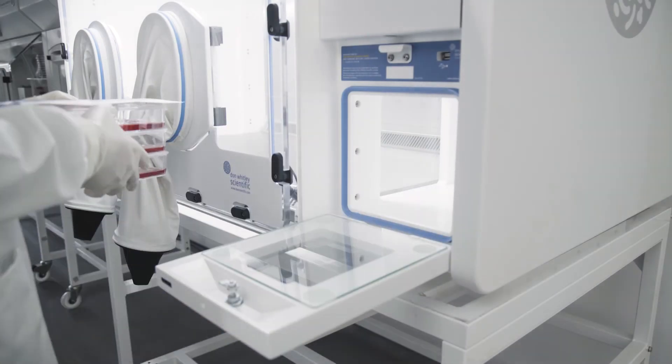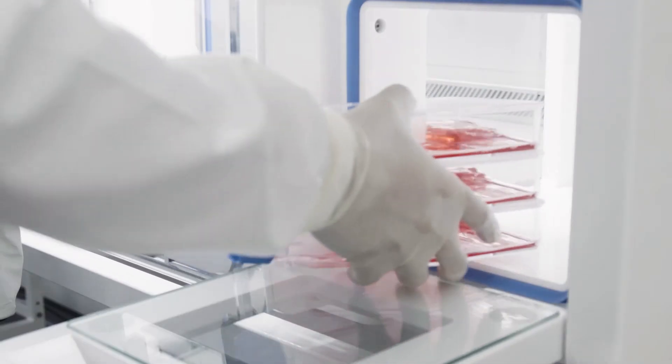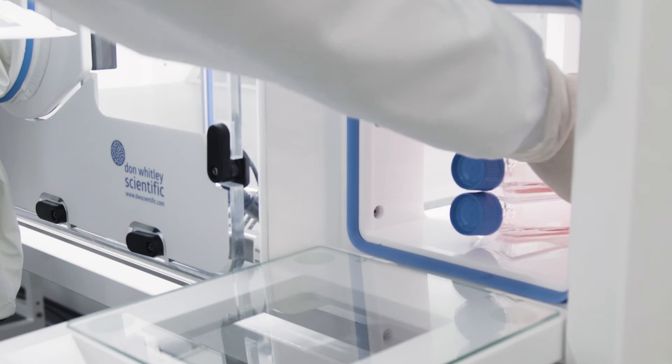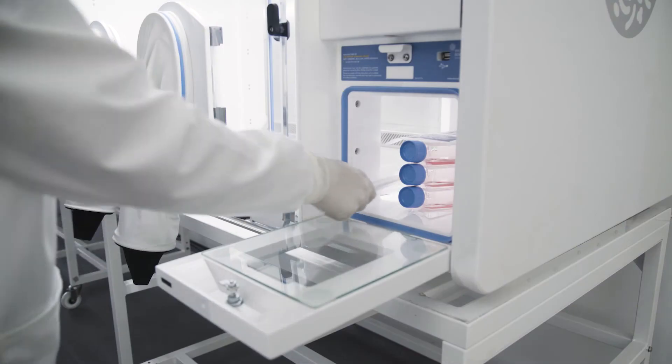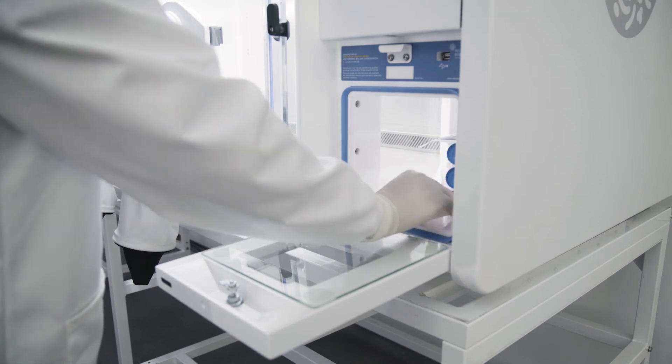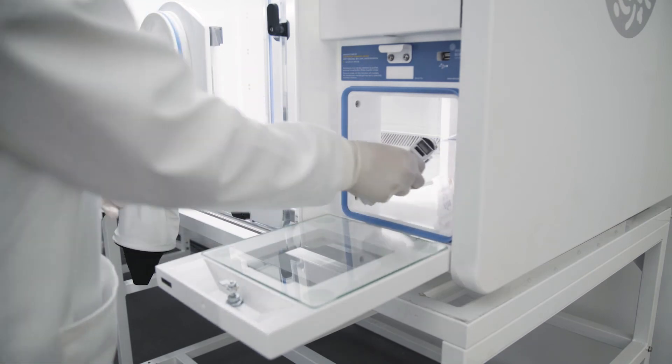Items are brought into the workspace through an H14 HEPA filtered airlock, which over the course of a 2 minute flush cycle reduces the levels of oxygen and background particulate to ensure the internal environment is never compromised.